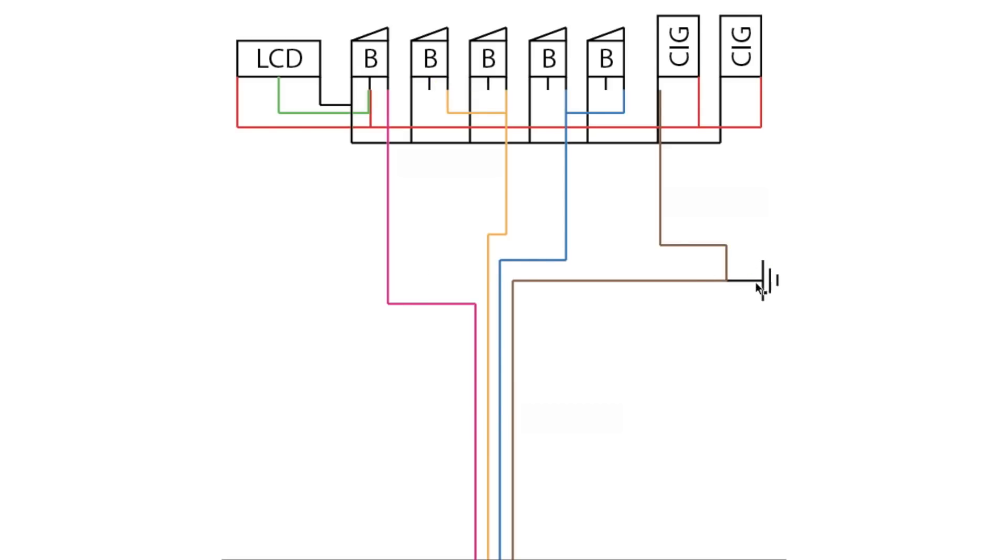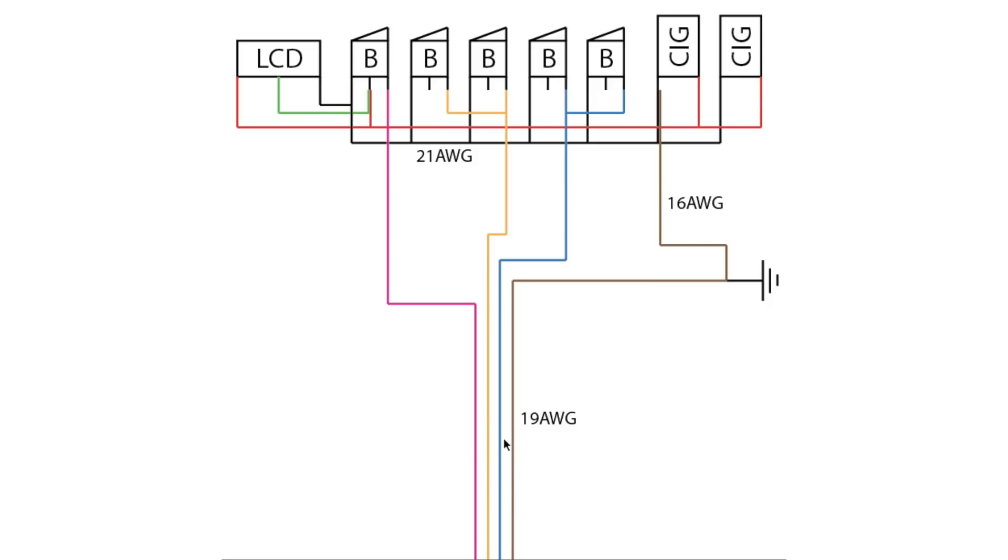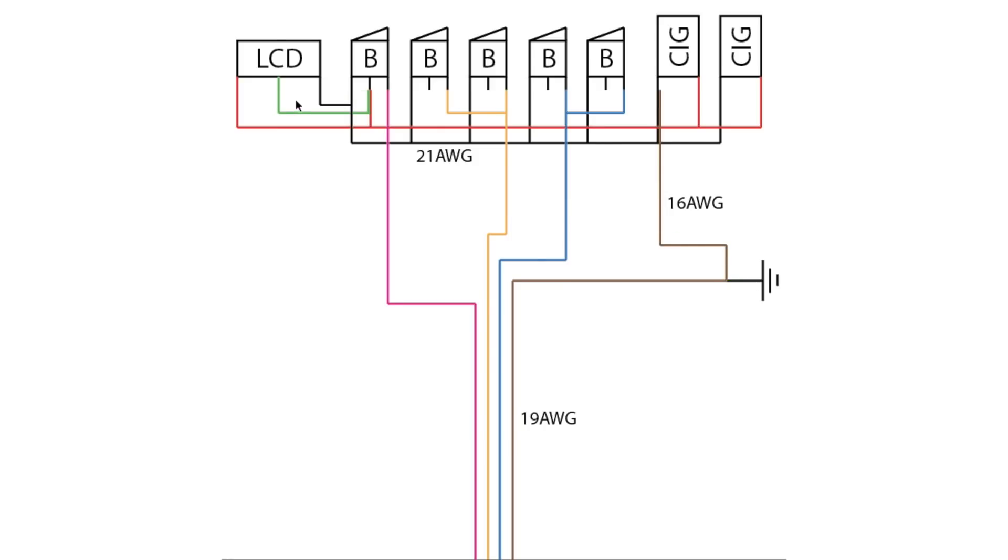Lastly, I'll quickly run through the gauge or thickness of wire you require. The easiest way to explain this is the four cables that power the whole control panel and the ground that come in from the battery - they are all 19 AWG. The only 16 AWG cable you're going to need is to come off the negative directly off the negative port of the cigarette lighter and go directly to the ground. Then the rest of all of these cables, apart from the LCD monitor that's already pre-wired, all these extra little cables are 21 AWG. Every wire has a current or voltage limit and each of these corresponds to how much these wires can take safely without burning out or causing issues.